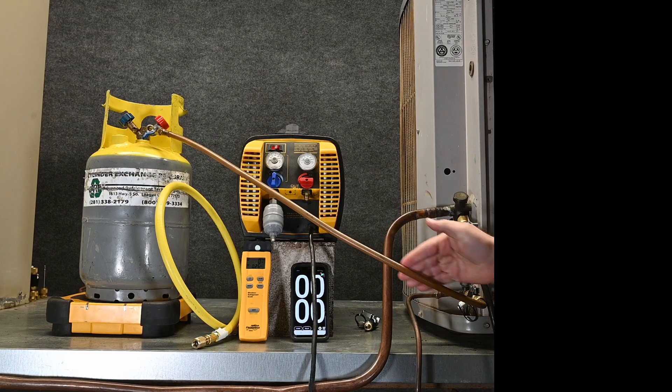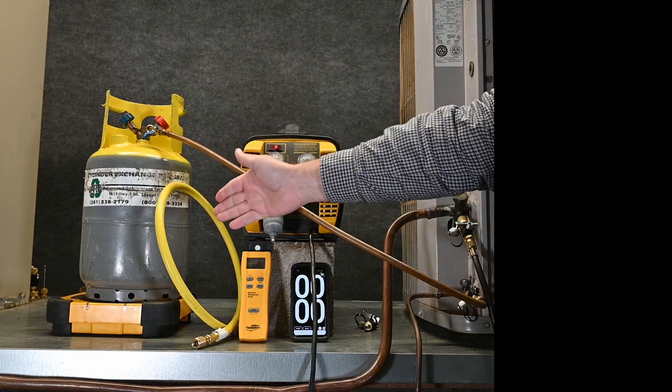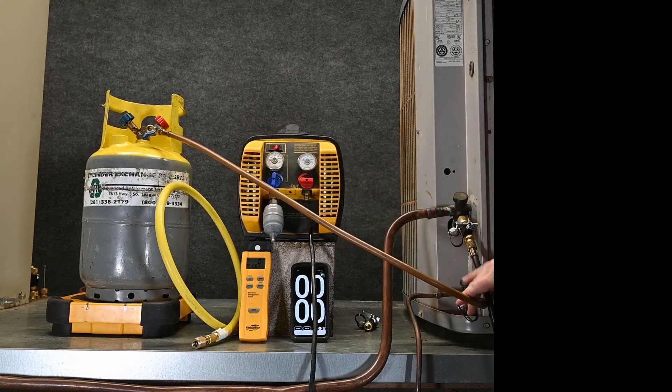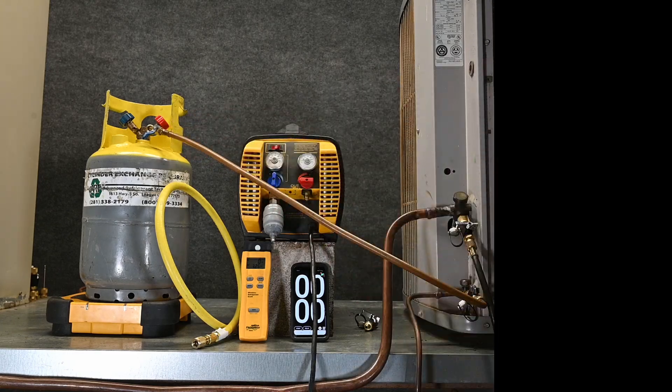Now because I only have a quarter-inch hose going to this recovery tank, that straw also being a quarter-inch size isn't going to slow us down, so I'm going to leave the tank upright. So this way we've connected the liquid line to the liquid port of our recovery tank.